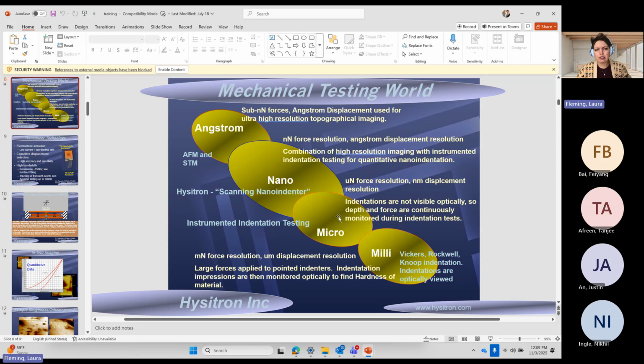What I like to point out is what ours does, this Hysitron scanning nano indenter. We're kind of in between. We're straddling this area of the mechanical testing world where we still have that nanonewton force resolution and angstrom displacement resolution, but we also have a combination of high resolution imaging. So our system can also image a sample surface to give us that information. Are there any questions about this slide?